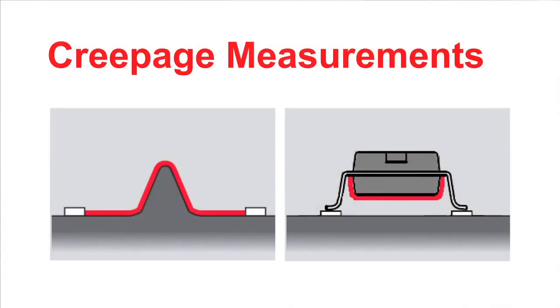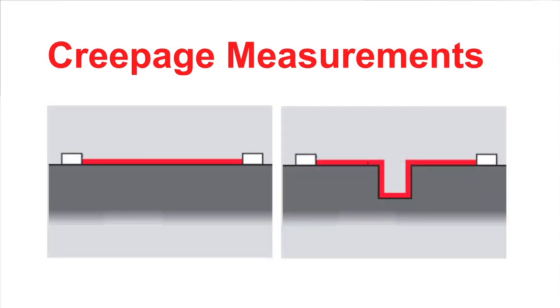Now let's talk about creepage. Creepage is the shortest distance between two uninsulated conductors along the surface of an insulating material. Let's look at the diagram of different examples of how to measure the creepage distance. You can see the creepage is the measure of the shortest distance along the surface between uninsulated conductors.